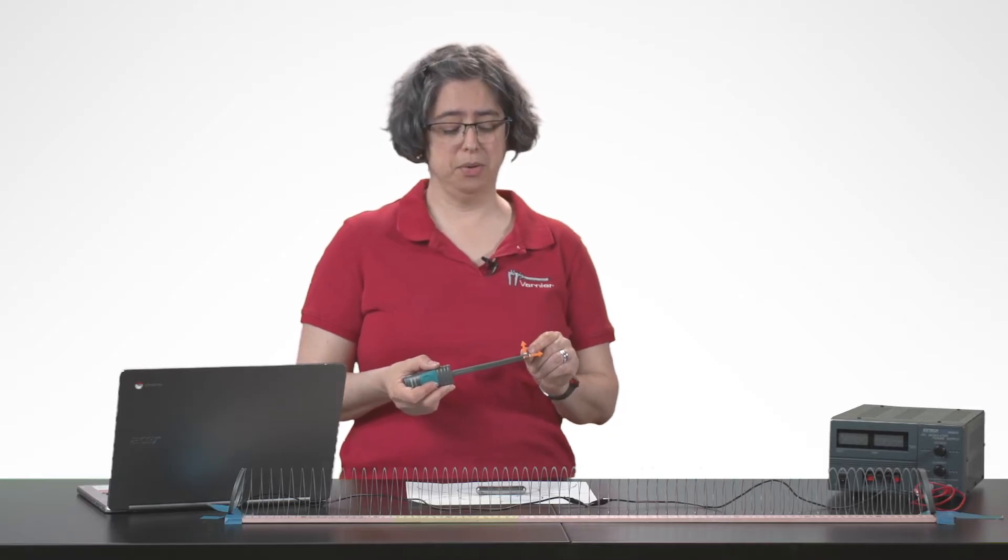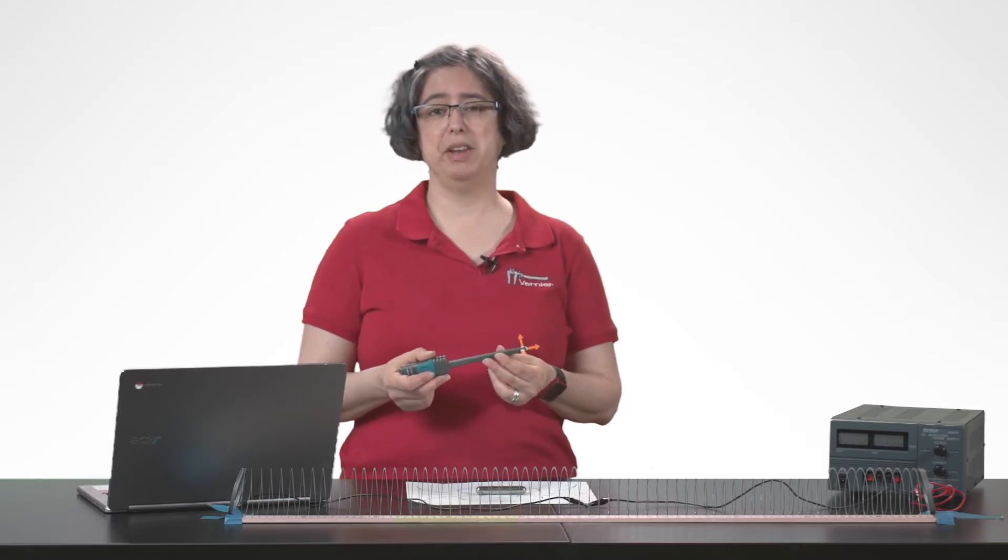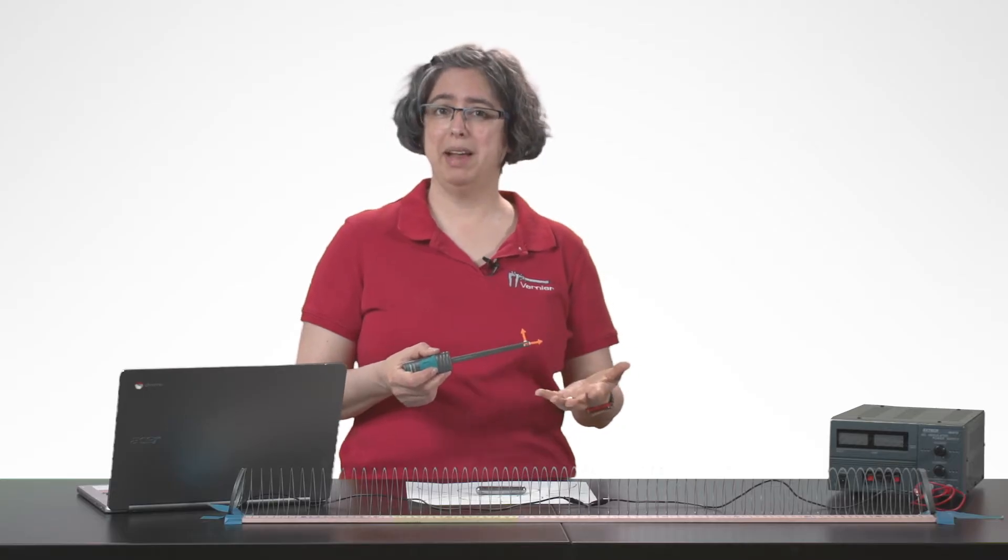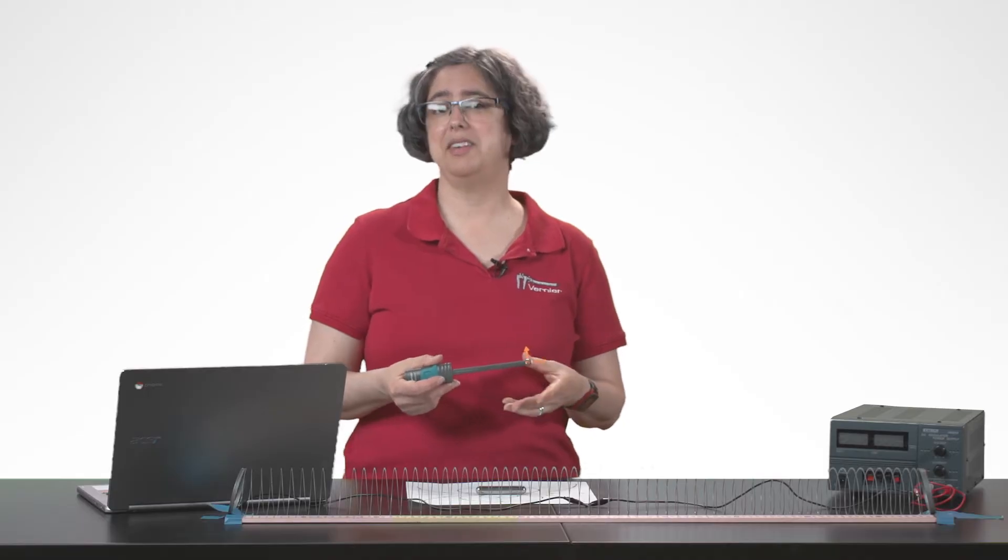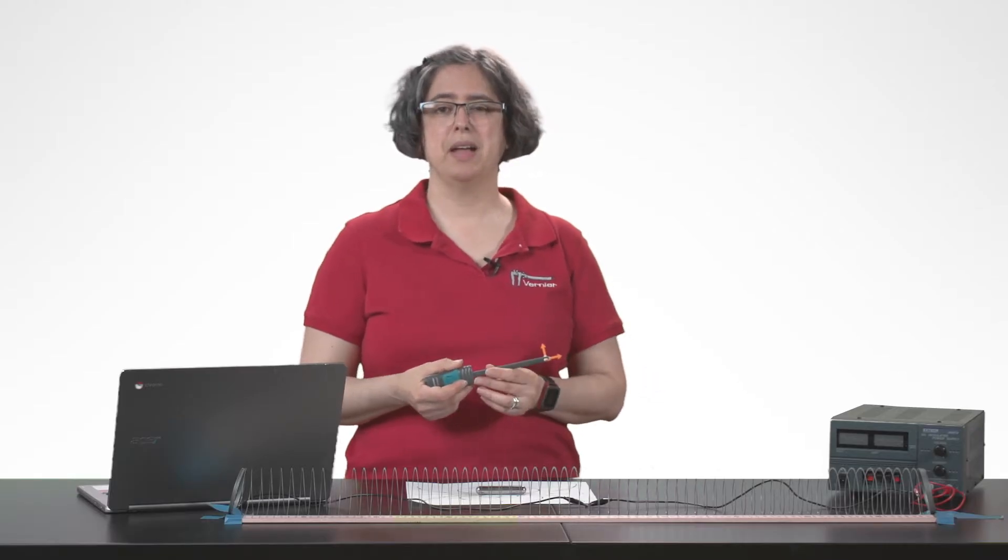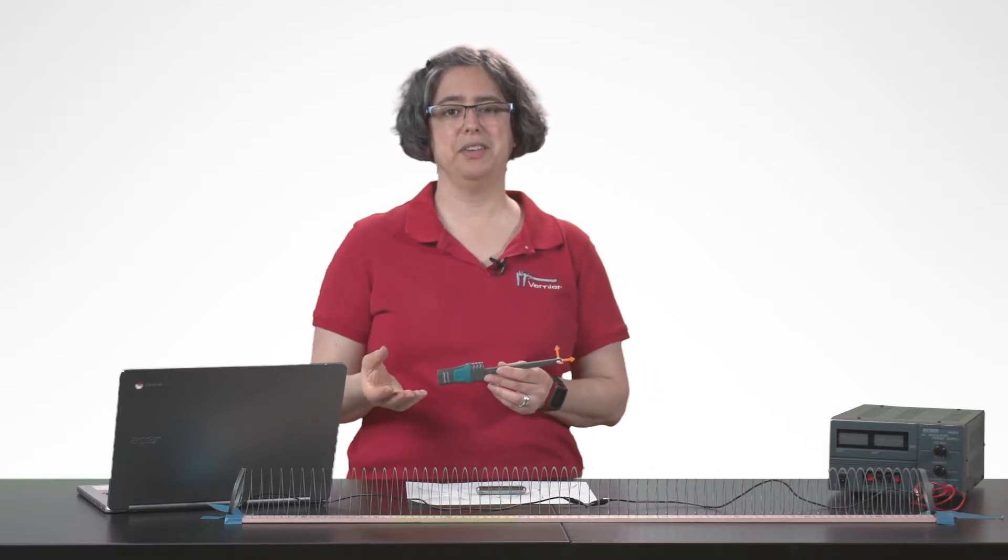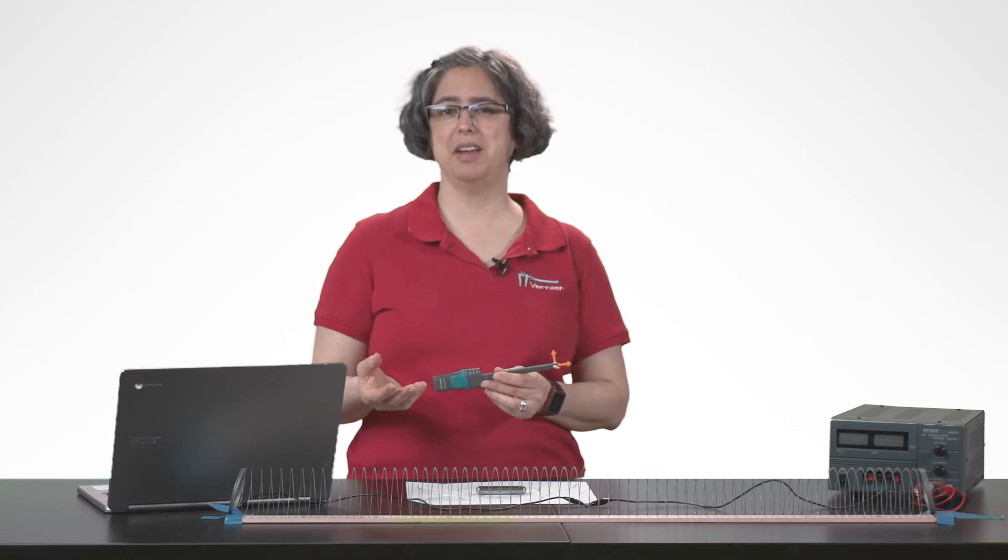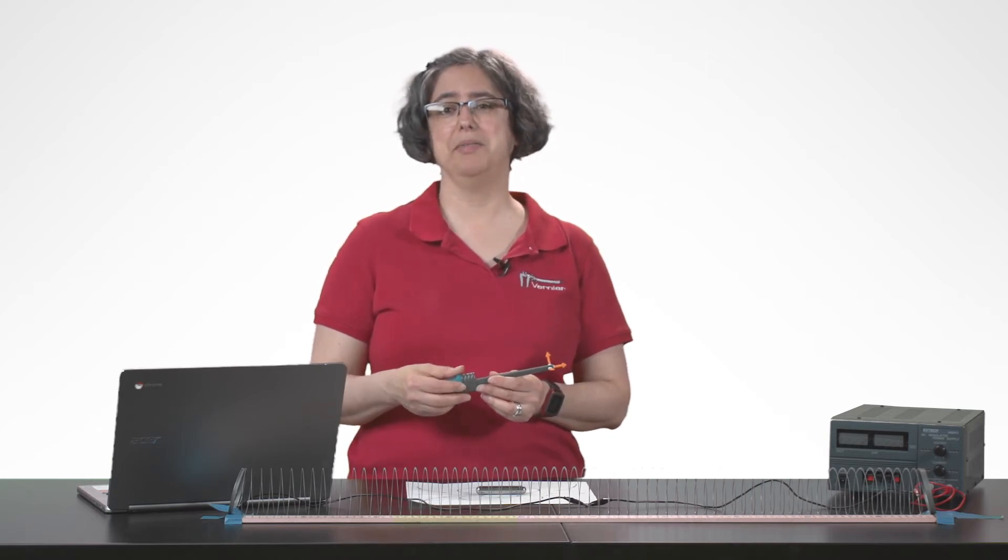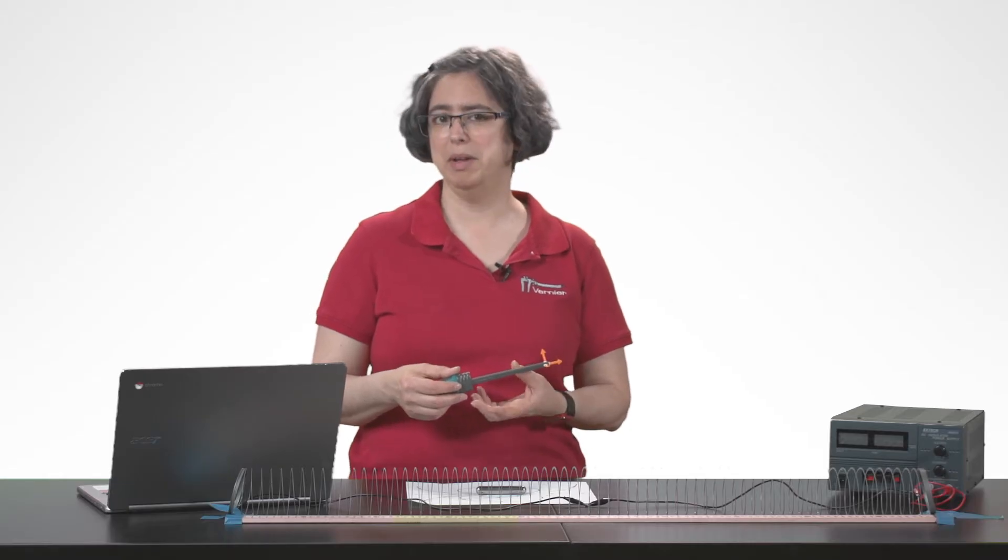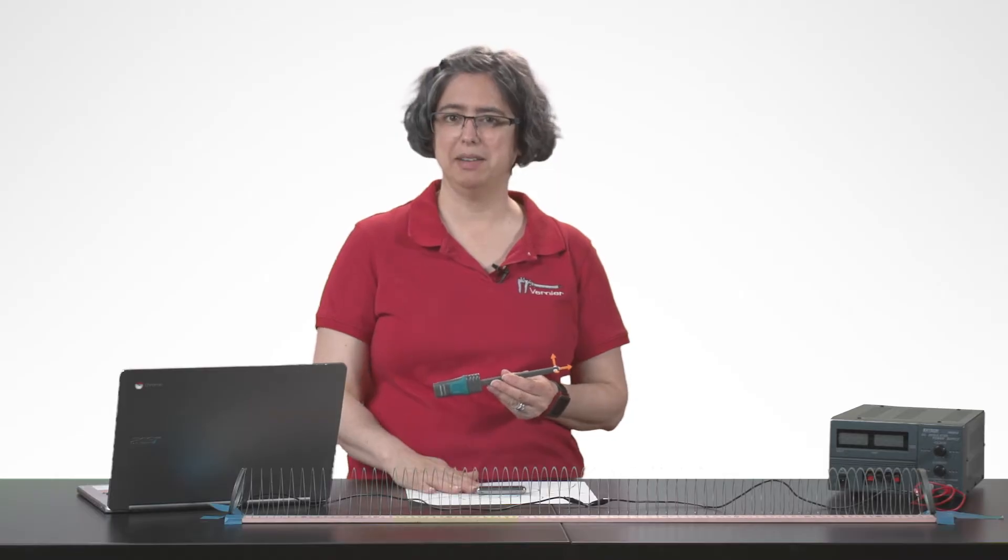Use the plus or minus 5 millitesla setting for lower magnitude magnetic fields, such as the magnetic field of the earth or of a solenoid. Use the higher channels, the plus or minus 130 millitesla channels, if you're measuring magnetic fields of permanent magnets, especially neodymium magnets and strong cow magnets.